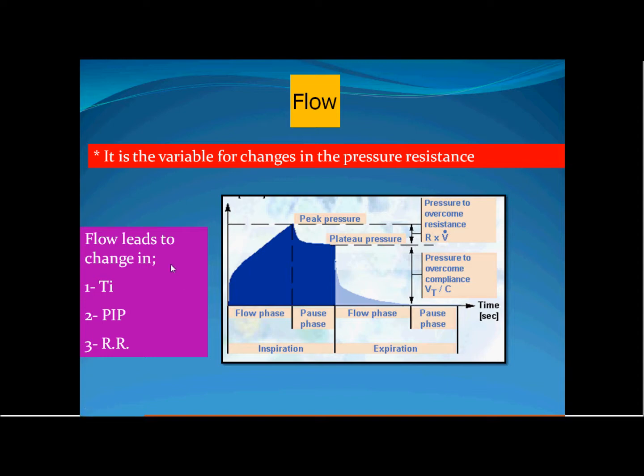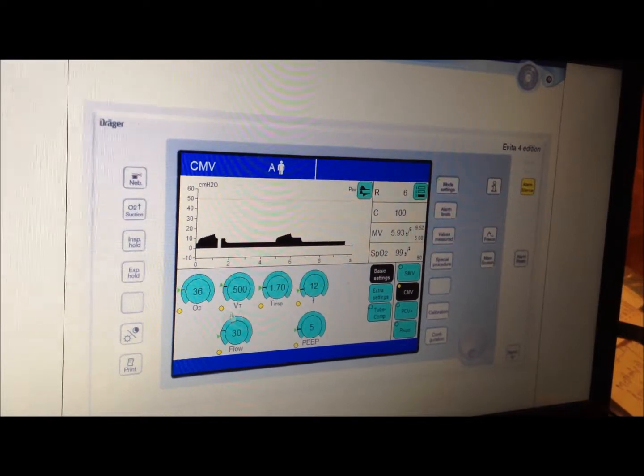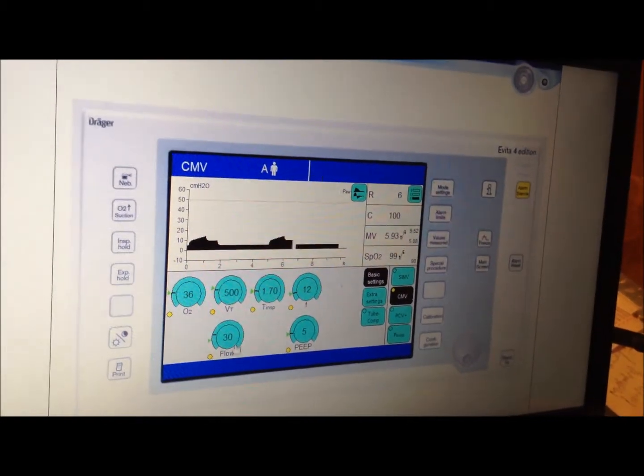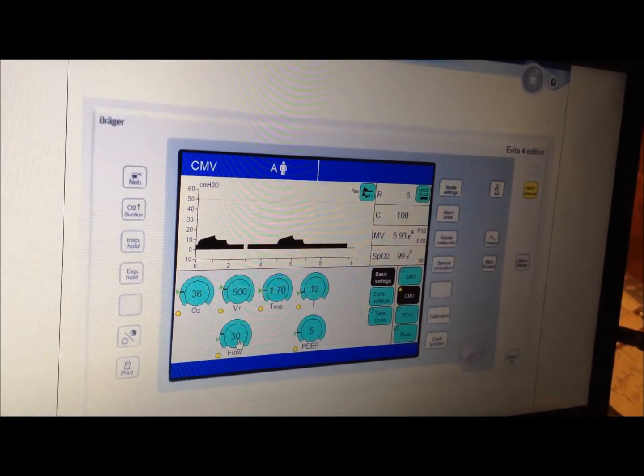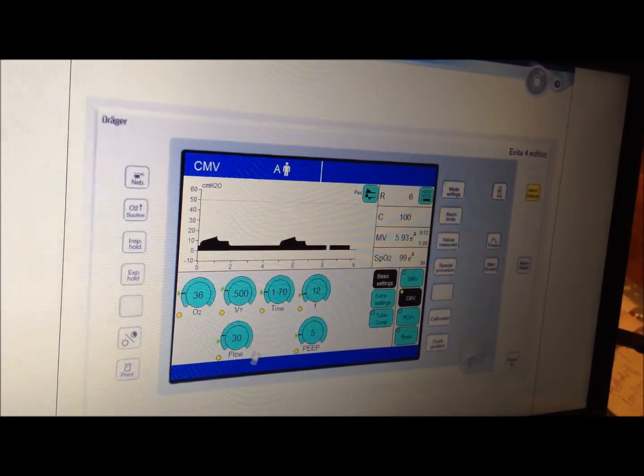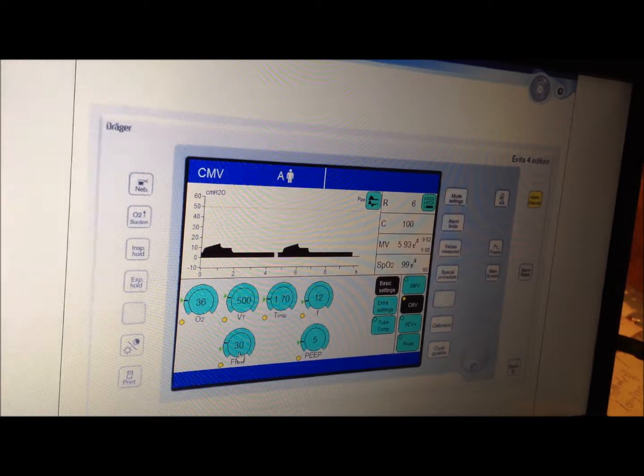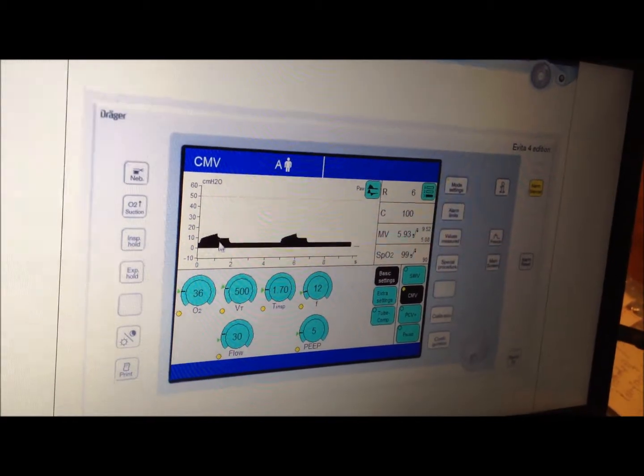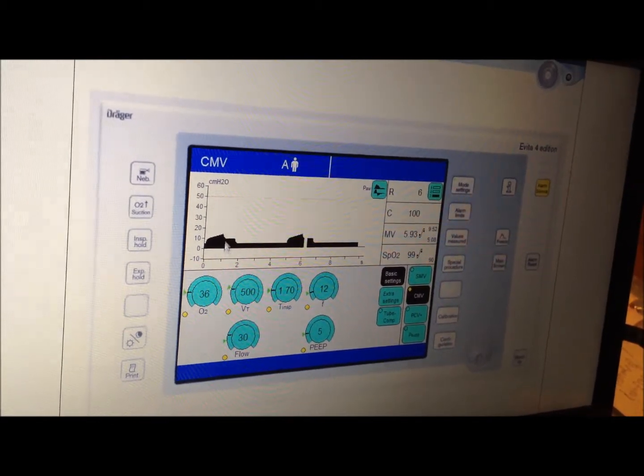In this volume-controlled ventilation example, the flow is set at 30 liters per minute, which equals 0.5 liters per second. The tidal volume is 500 mL (0.5 L), so this tidal volume will be delivered in one second. This flow therefore determines the time for delivery of the preset tidal volume.